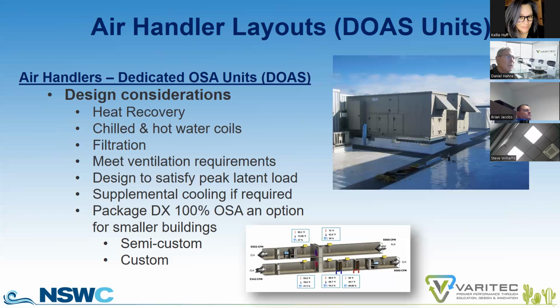Anyway, these 100% outside air units, because we're supplying 100% outside air, those buildings also require that we exhaust air from the building. Well, we don't want to take all that conditioned space air and then just dump it outdoors. So a DOAS unit is a dual tunnel unit that puts a heat recovery wheel in the unit that actually preconditions the outside air before it sees the cooling coil, with the exhaust air leaving the building. There are two types of heat recovery solutions. There's sensible only, which comprises plate and frame heat exchangers, or you could do a sensible only wheel. And then there are enthalpy wheels that actually meet some of the latent capacities in preconditioning the outside air, as well as the sensible. So we always see heat recovery devices in a 100% outside air unit.